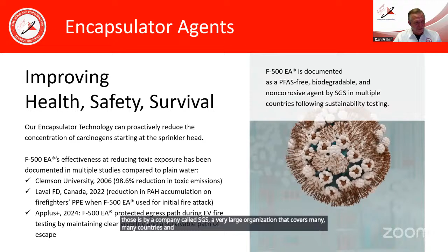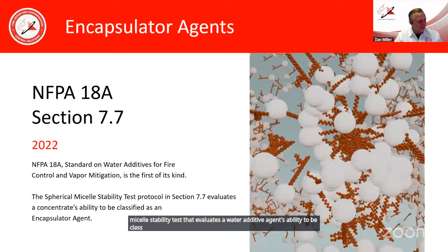NFPA 18A is an NFPA standard on water additives for fire protection and vapor control, and it's the first of its kind to cover encapsulator agents. There's a test within NFPA 18A called Section 7.7, the Spherical Micelle Stability Test, which evaluates a water additive agent's ability to be classified as an encapsulator agent. Annex 4.3 of that same standard references the ability of encapsulator agents, through extensive third-party testing over many years, to succeed at lithium-ion battery fire suppression, encapsulation of flammable electrolytes, and reduction of explosive and toxic vapors. That testing demonstrates the ability to stop thermal runaway propagation, and it's been conducted by many third-party organizations worldwide since 2008.